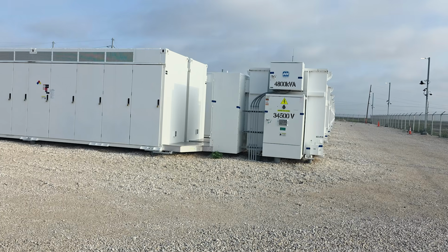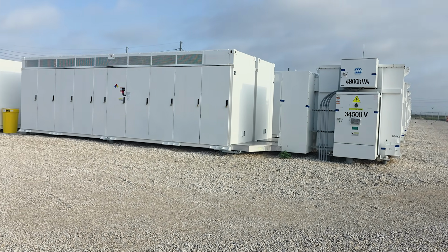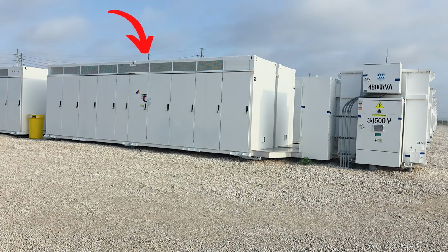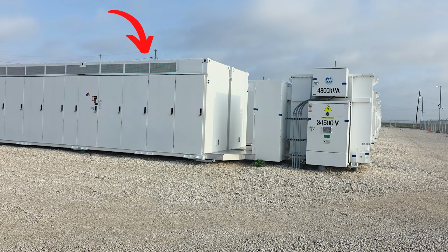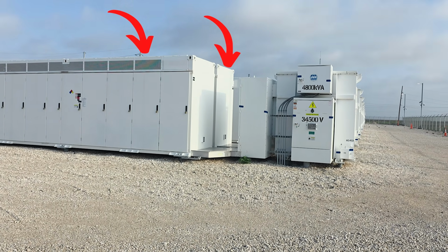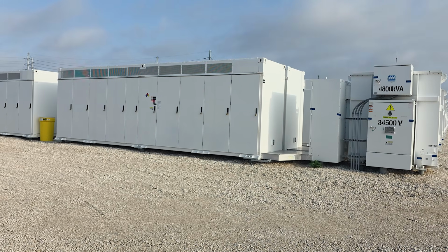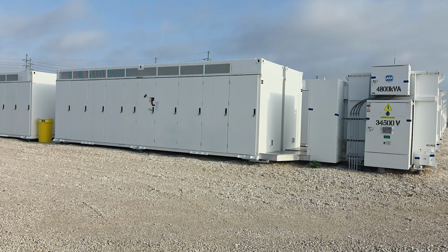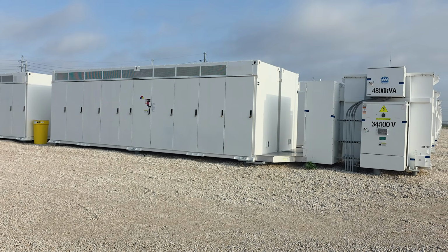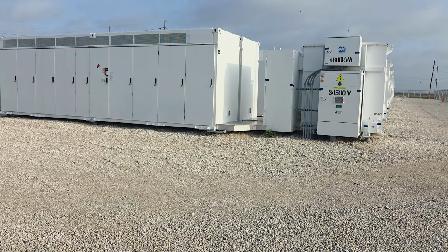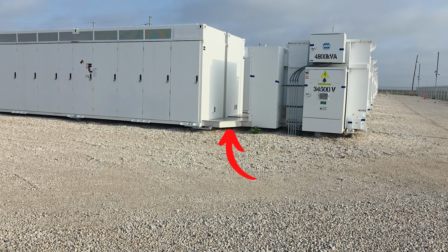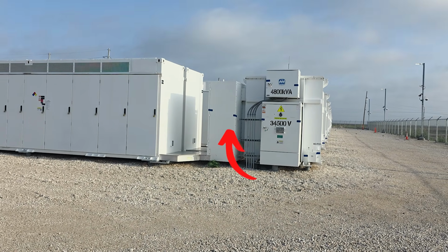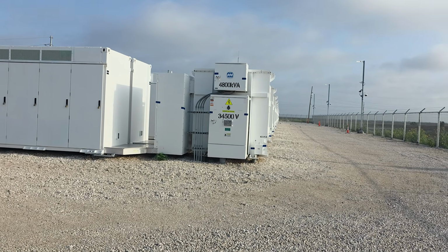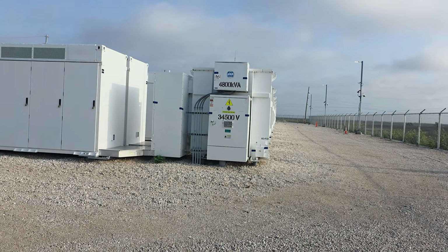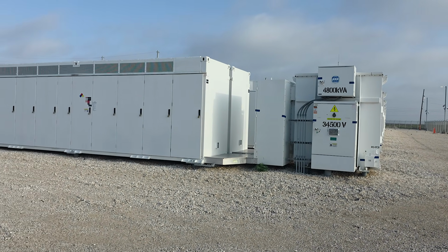So in this particular case, you have 2 batteries. We're looking at one, and in the center of the screen, right there where the crack is, that's the second battery. So you've got 2 battery banks with an inverter that's integrated into the skid that you're looking at. You've got down low the cable tray. Those are where the 480 volt cables come out into the secondary side through the transformer and out 35 kV. So from there, we will get a little closer.